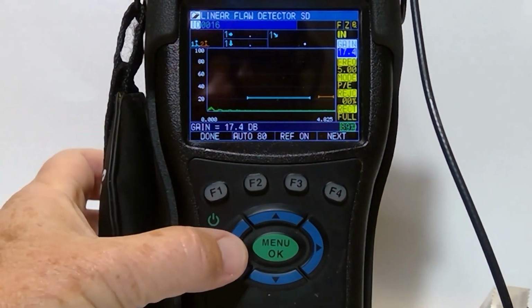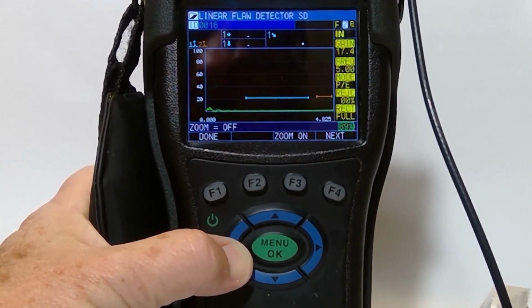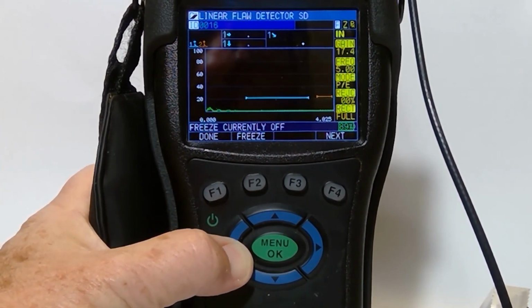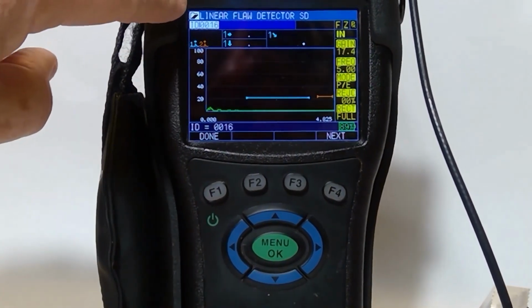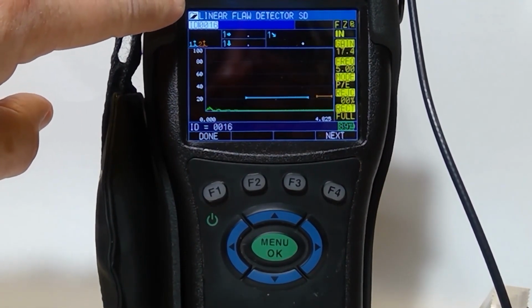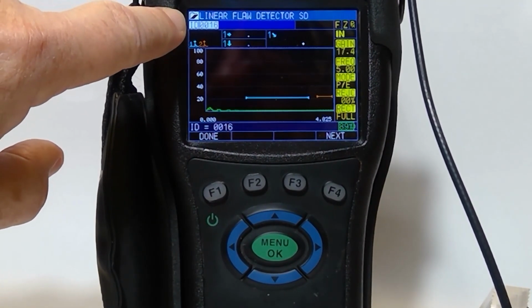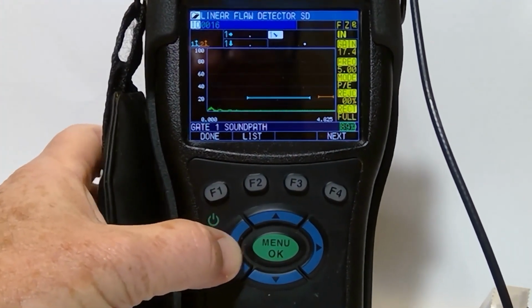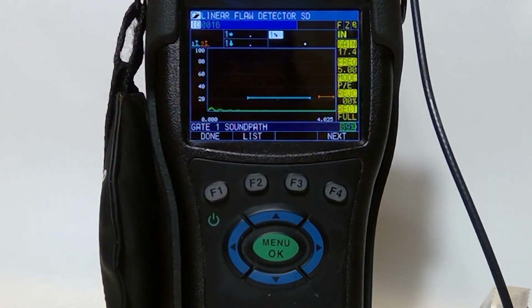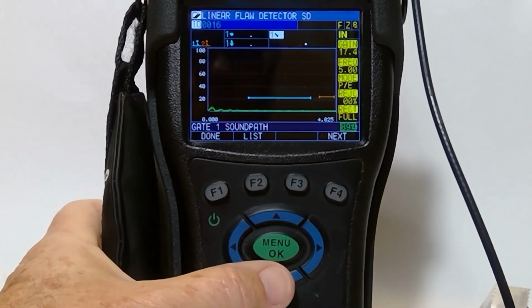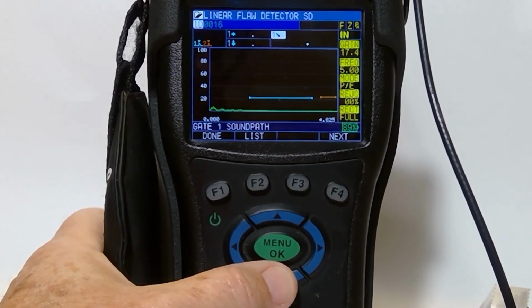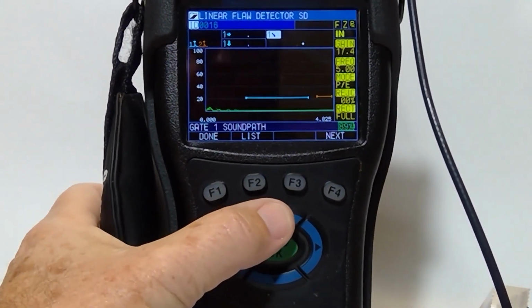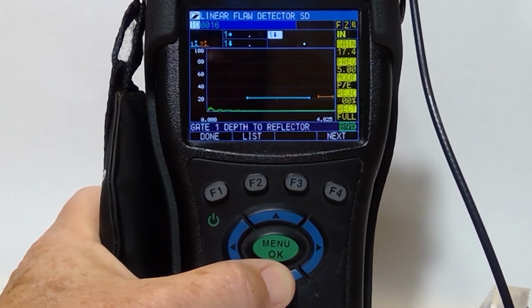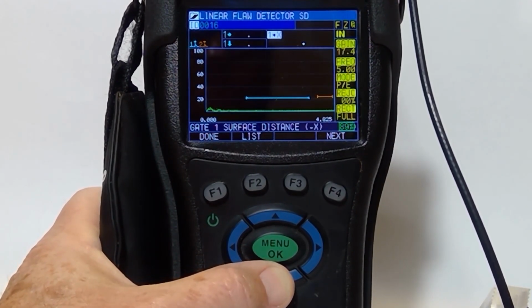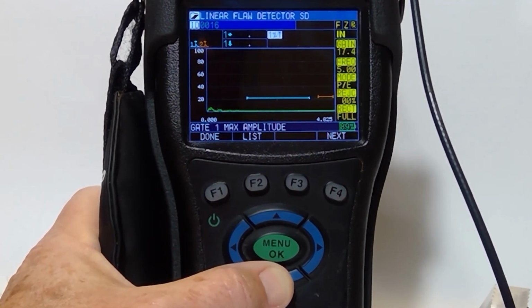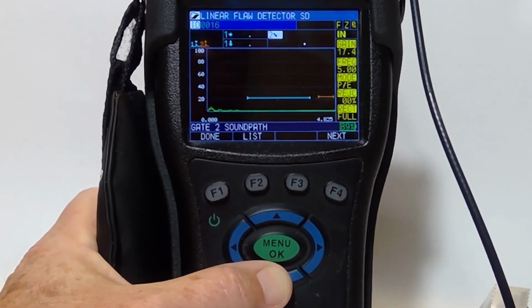Some of the other features you can see, if you notice above gain, we have zoom, we have freeze, and we can also look at the ID. If you notice at the top, this is the file that I'm using. It's linear flaw detector on the SD card. My next ID is 0016. Now it gives me the information for my sound path. If I wanted a different reading in the sound path or in this main thickness box, I can change that with the left or up or down arrow key. It's off, sound path, depth to reflector, surface distance, reflector leg, minimum depth. So it gives me many functions to use.